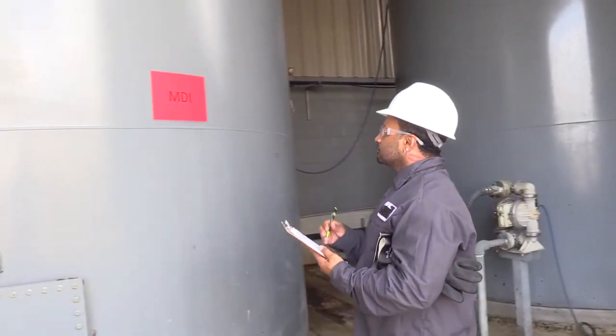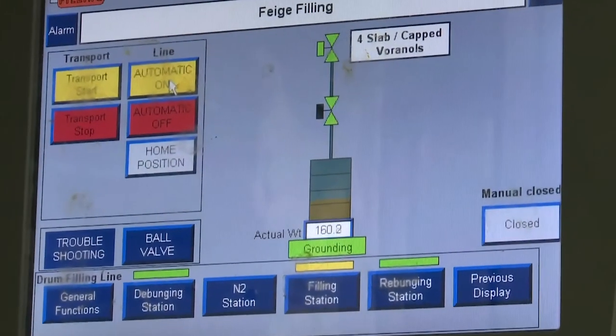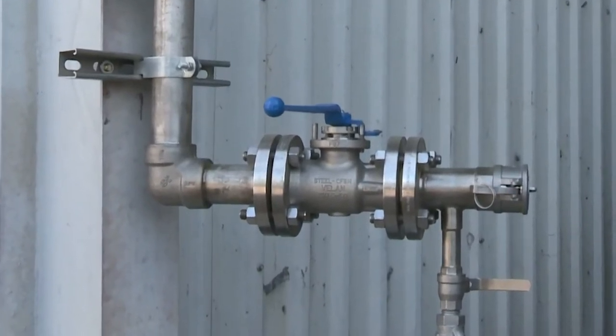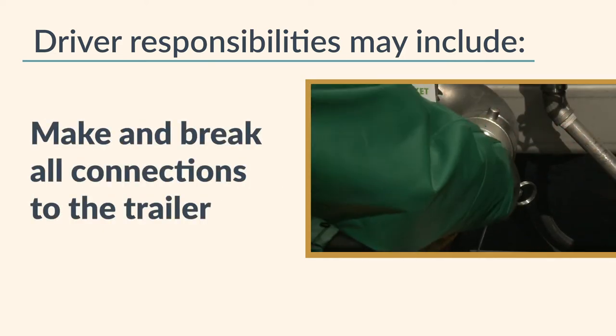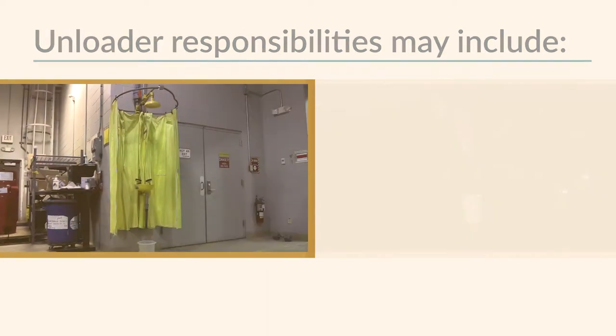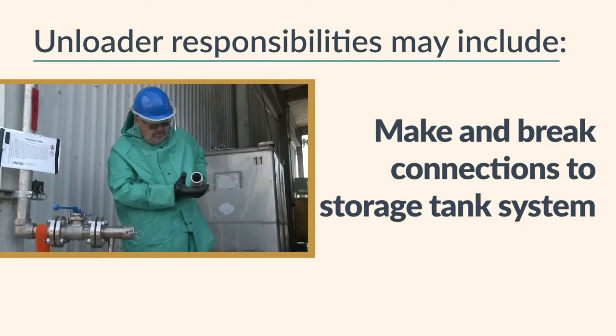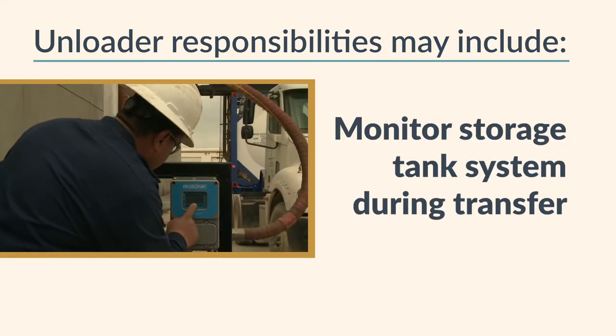Once the paperwork and tank truck checks are complete, the next step is to check your own equipment. If the contents of the tank truck are to be offloaded into a receiving tank, make sure the tank is the correct one for the product and that there is enough room to hold the shipment. Clearly identify the unloading connection on the receiving line. Driver responsibilities may include the carrier showing the customer how to shut down in an emergency, make and break all connections to the trailer, operate trailer valves, and attend the trailer throughout the transfer. On the receiving side, responsibilities may include showing the driver the location of the safety shower and eyewash station, making and breaking connections to the storage tank system, operating valves in the storage tank system, and monitoring the storage tank system during transfer.